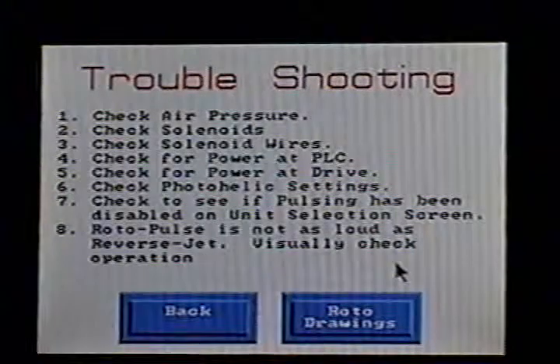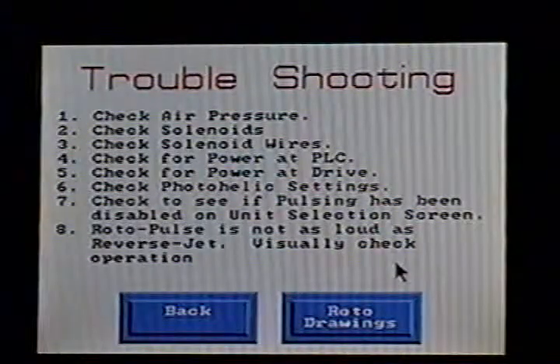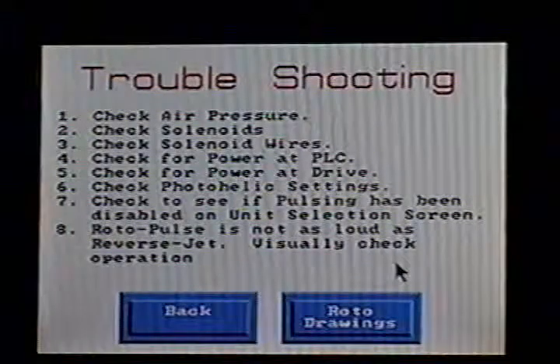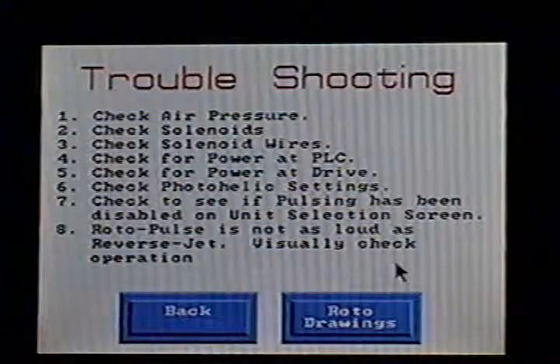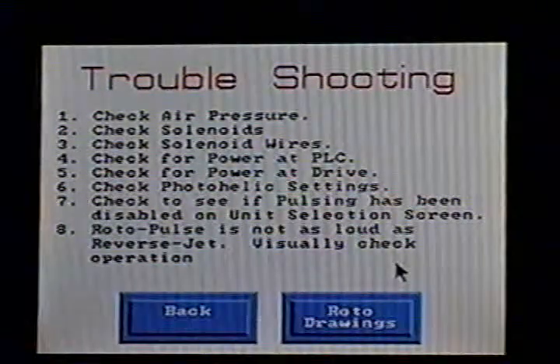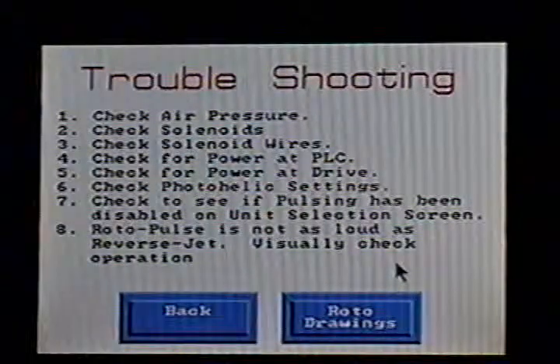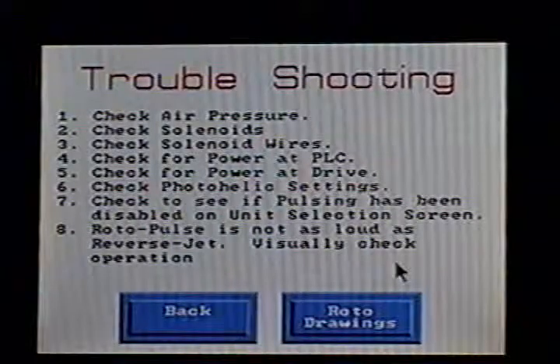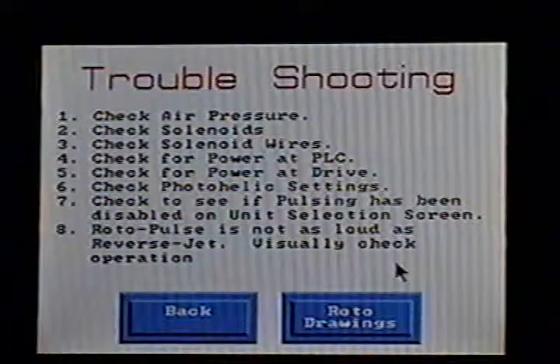Now let's say no. Well, do you have air pressure? Are the solenoids wired? Do you have power to the PLC? Do you have power at the drive? Maybe your photohelic was turned on and you think it should be pulsing, but pulsing has been disabled. There's an option to disable pulsing. This will help you troubleshoot and walk through things. If you're on the job site, it'll help you easily go through and find the problem. It'll help the customer.